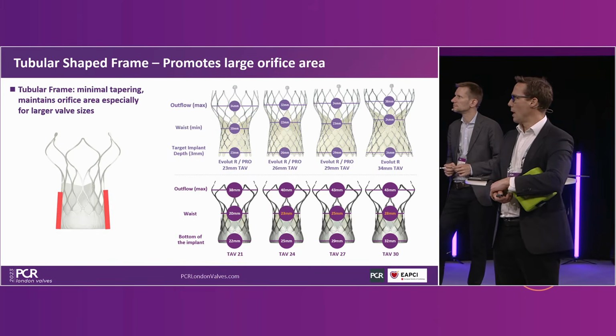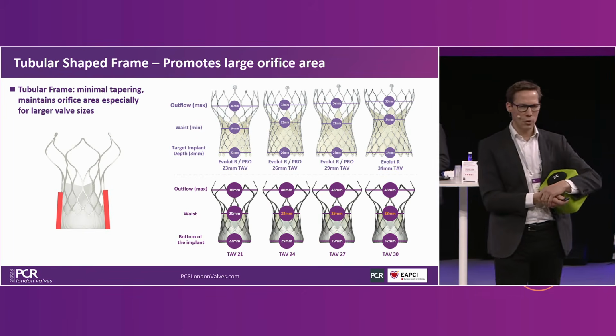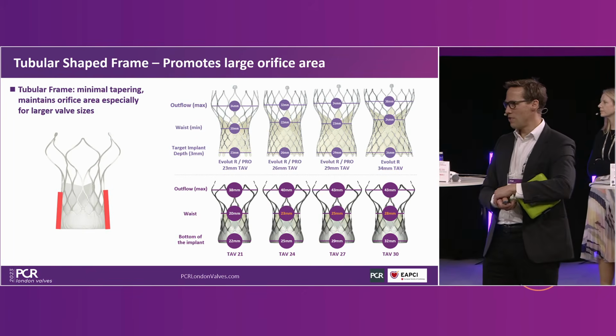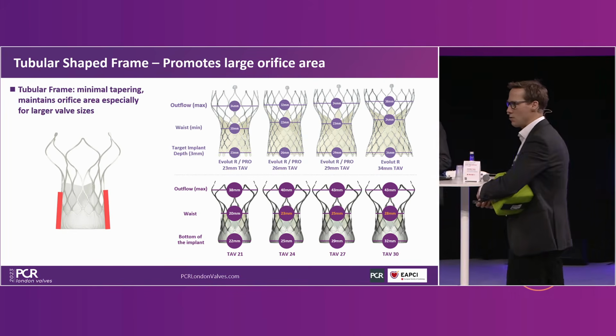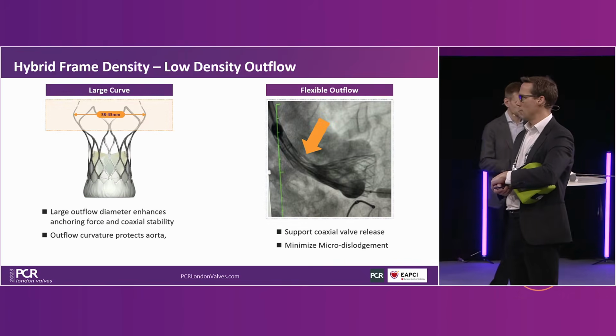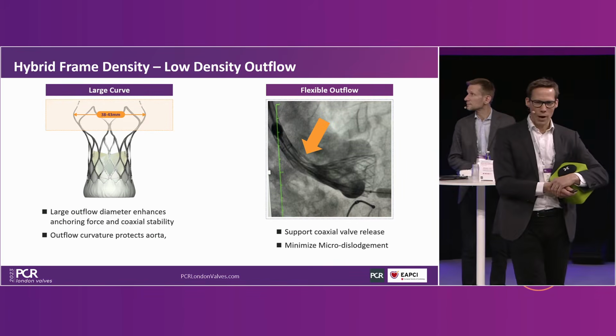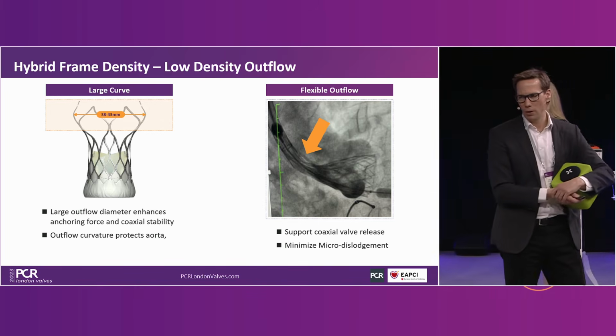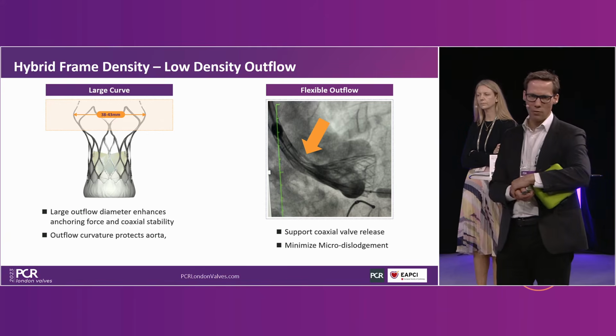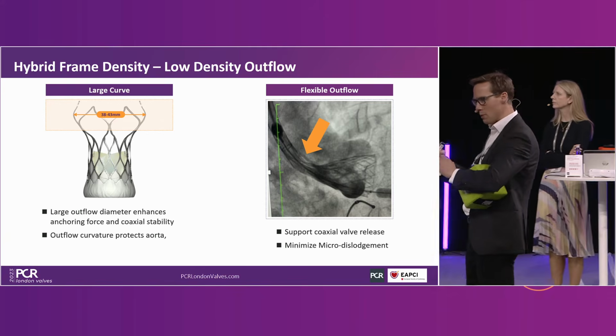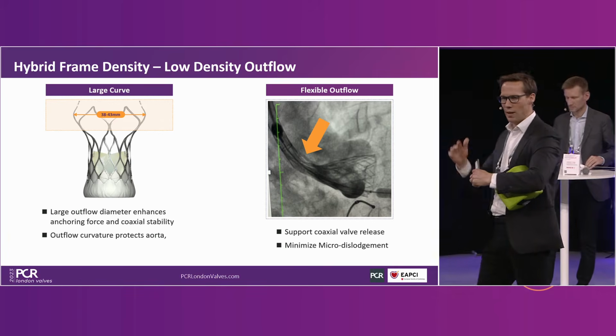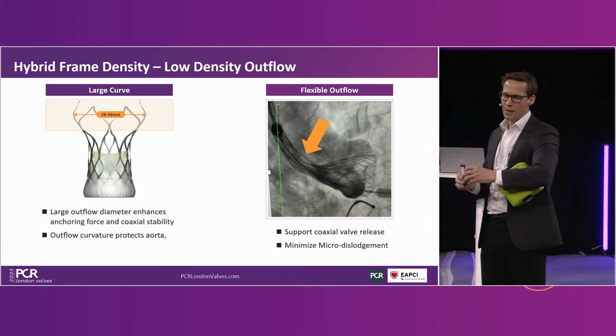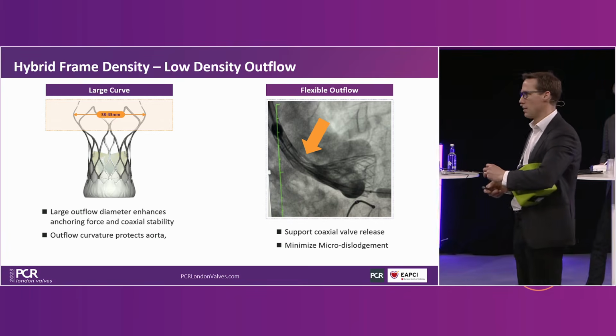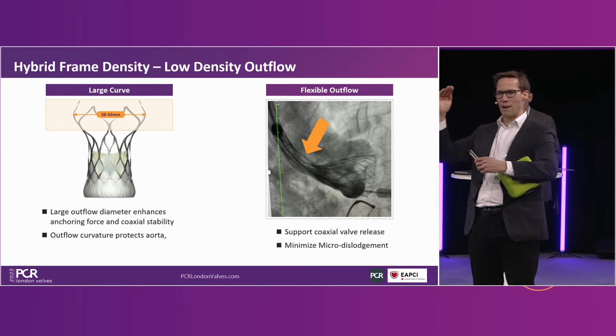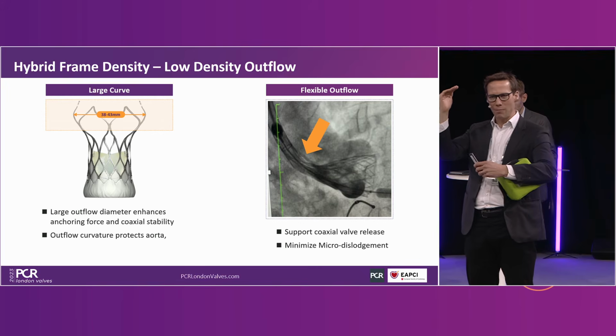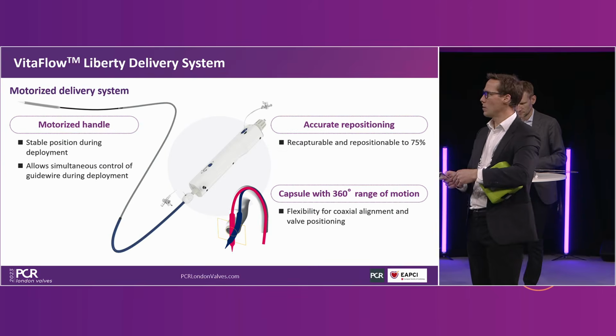I mentioned that the tubular shape gives you a good orifice area, but again, if you have narrow sinuses, with these types of valve designs you need to be a little cautious in terms of the risk of coronary occlusion. The picture on the right is a very common picture with this device as you're deploying it. You'll notice that there's almost a bend in the center of the frame, and that's because of the difference between the very stiff bottom portion of the valve and the much more flexible top portion. That makes it quite a nice valve for, for example, horizontal anatomies. And another thing to notice is the way that the valve frame comes in at the top, and that we think is probably a little bit safer in terms of aortic dissection.